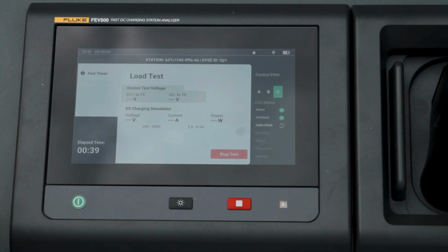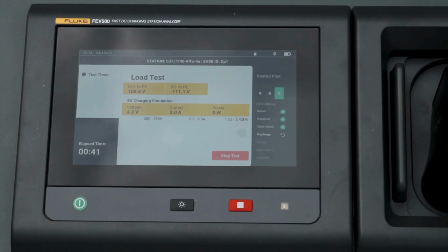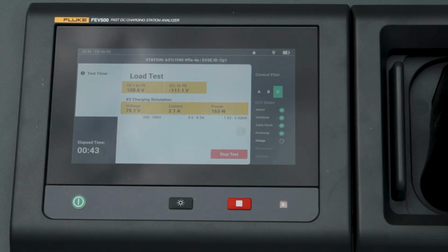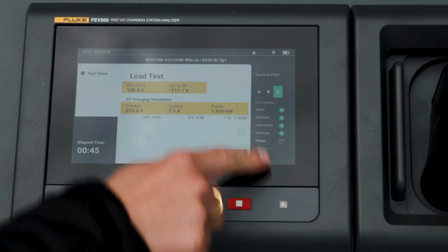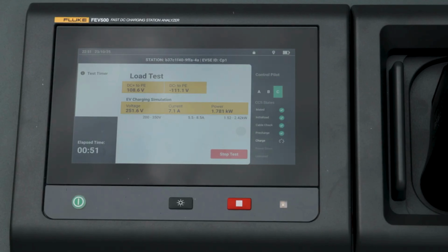So you can see over on the right-hand side all of the digital communication or charging states, the CCS charging states. So we're going through cable check, pre-charge, and of course into charge now that it's doing the load test. You can see our live results are coming in for voltage, current, and power. And then once it finishes the load test, we should have our pass-fail indications and move on to the next measurement.